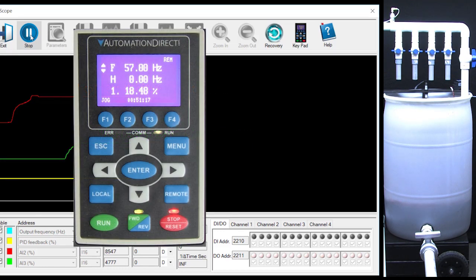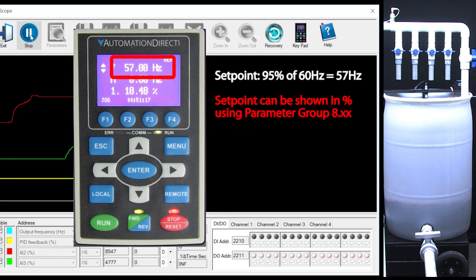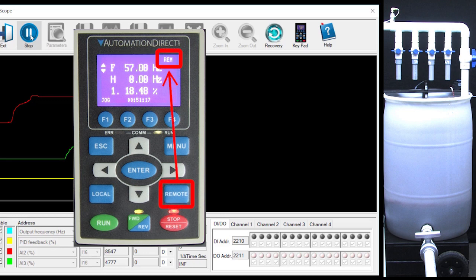By the way, you can show this LCD set point in percent using parameter group 8 if you want to. We're not going to take the time to do that but you can do it if you want to. Make sure the drive is in remote mode since we told the drive to only do sleep mode while in remote mode back in parameter 7.0. Turn on our water level LEDs to make that easier to see and hit run.